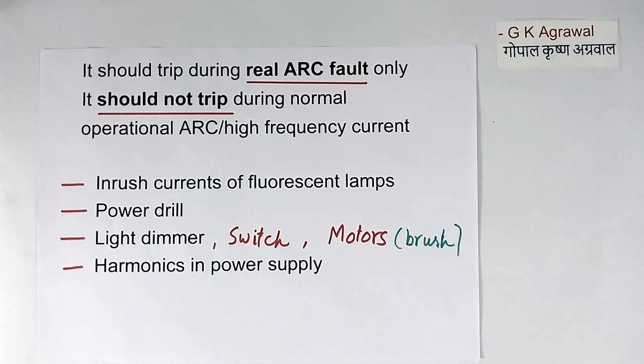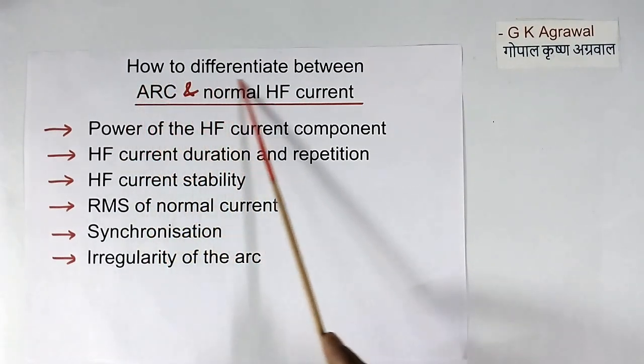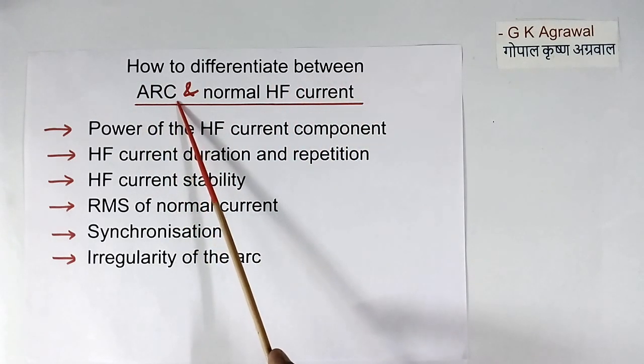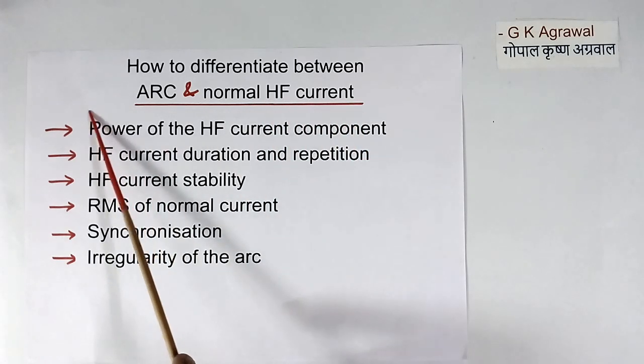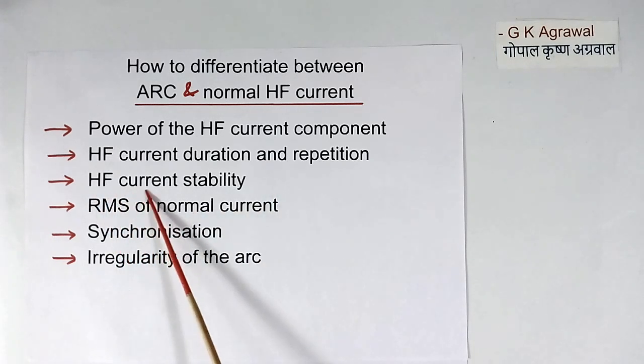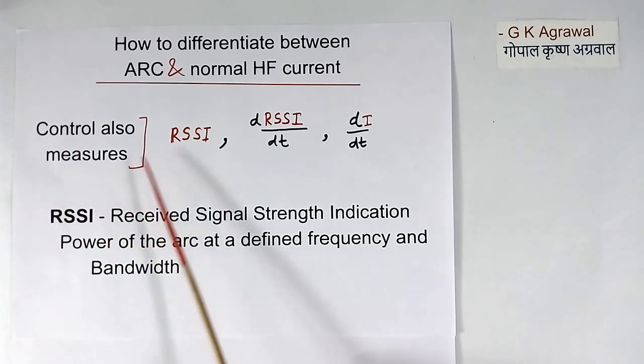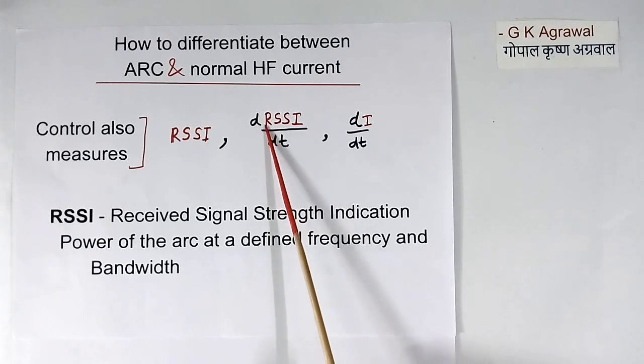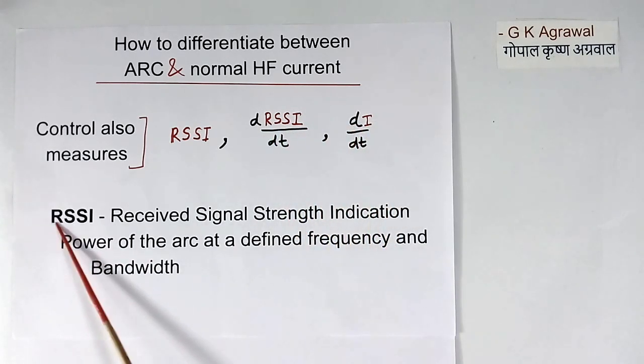How to differentiate between arc high frequency current and normal high frequency current? So controller measures all these things: power of the high frequency current component, high frequency current duration and repetition, high frequency current stability, RMS of normal current, synchronization and irregularity of the arc. Controller also measures RSSI, d/dt RSSI, and dI/dt. RSSI means received signal strength indication. Today I will not discuss about this in detail.